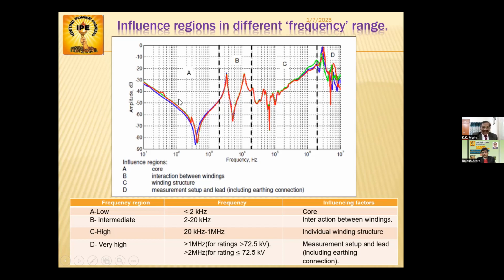So A region consists of the core. As you see, the curve comes like this and like that. Here you can see a yellow, blue curve and red curve. The red curve has got this notch. That is because of the reluctance path of the outer limbs of, say, A phase and C phase, whereas this is of B phase. It will not have any notch because the reluctance path is similar in either direction. So this is basically of the core, indicating the condition of the core.